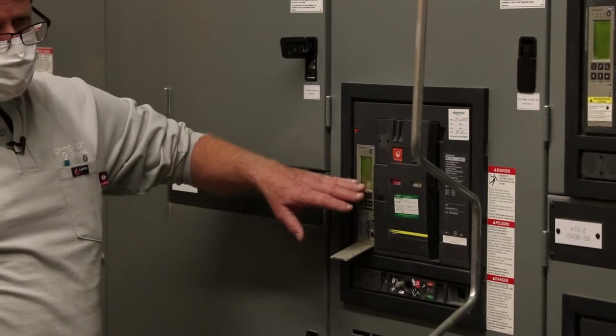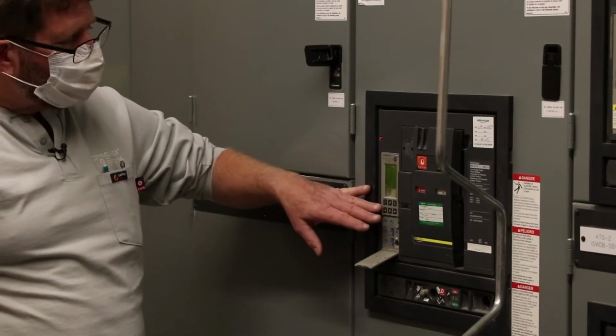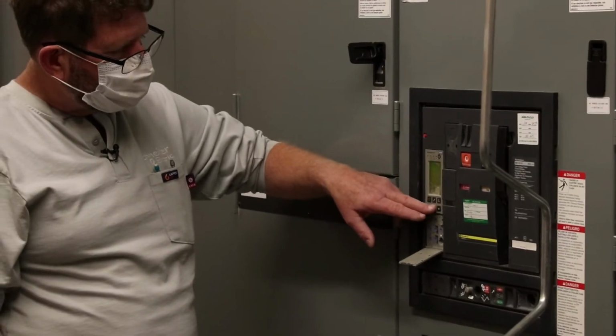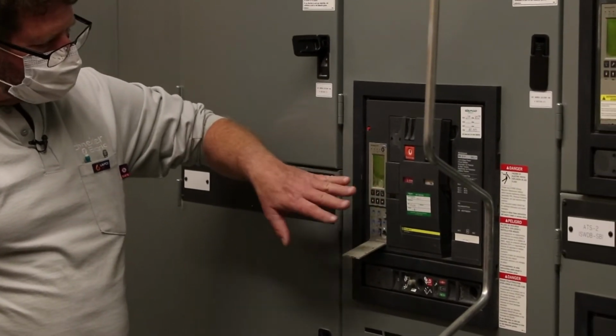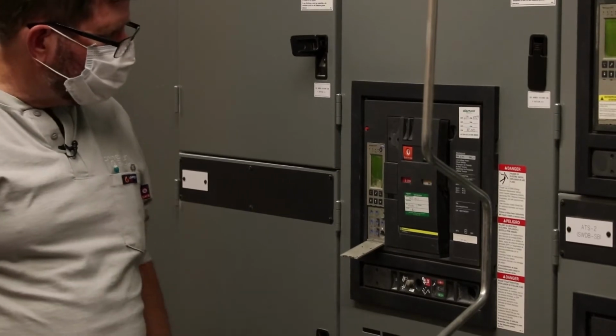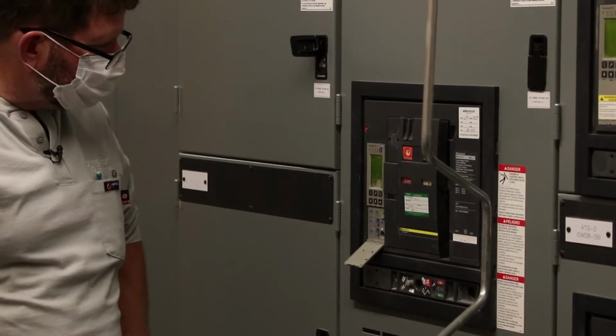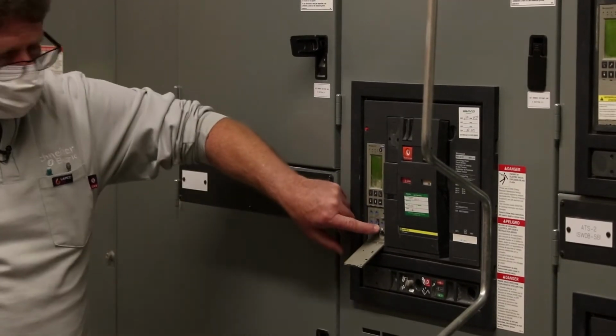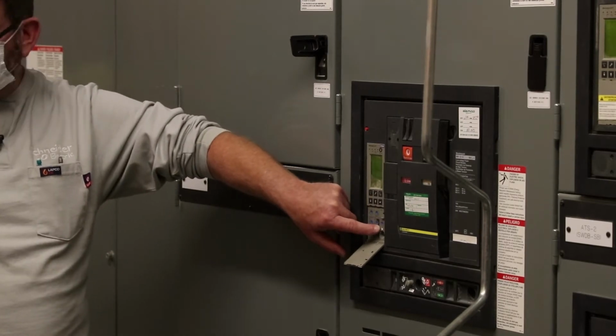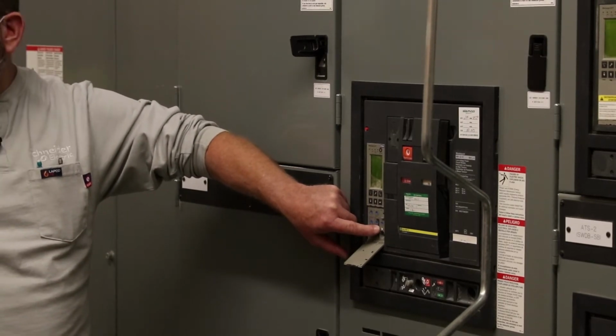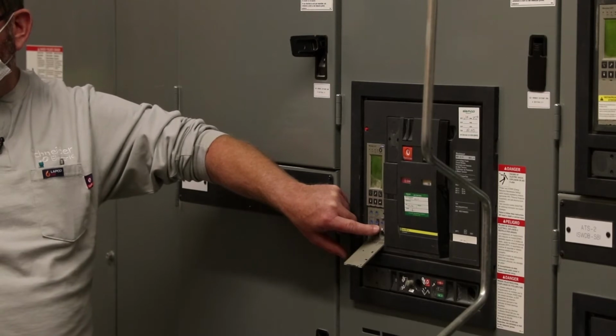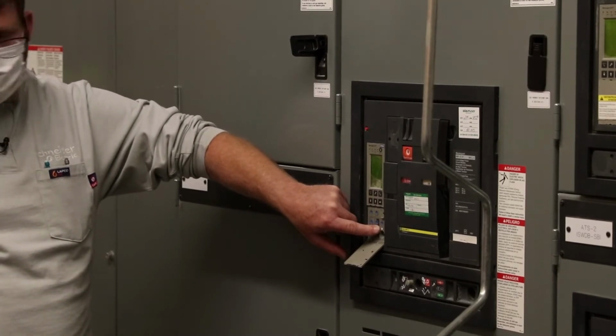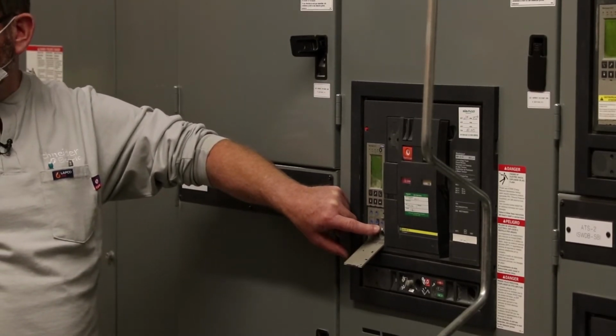So if you're coming in here in the middle of the night to try to figure out why a breaker tripped or what happened, you're not going to run any risk of tripping the breaker through these. Well, you would run a risk of tripping the breaker. There's a little white button here. That is a push test for trip testing the circuit breaker on ground fault. If you push this white button, the breaker will trip on ground fault.